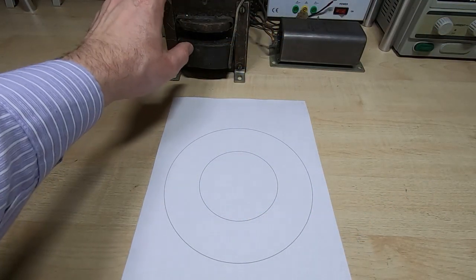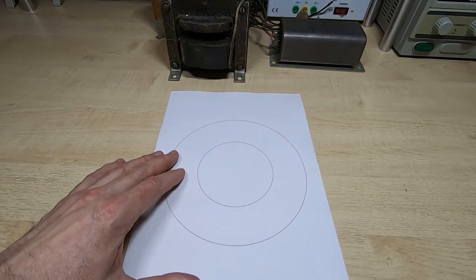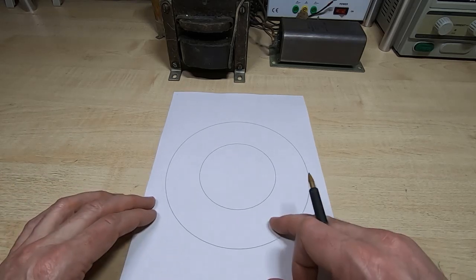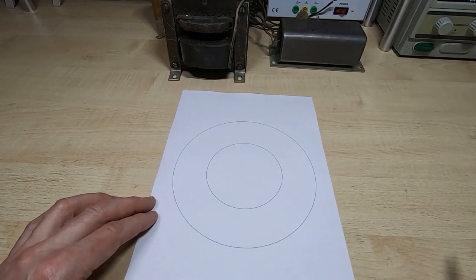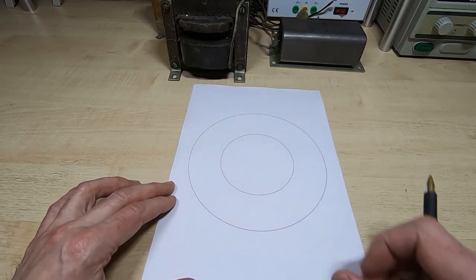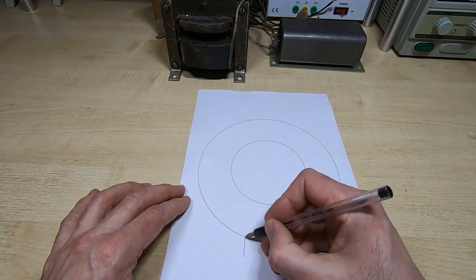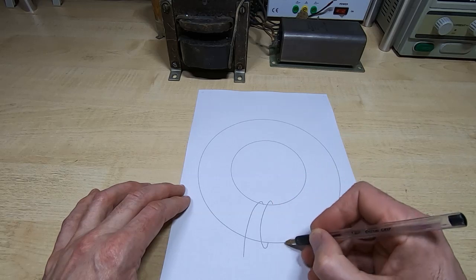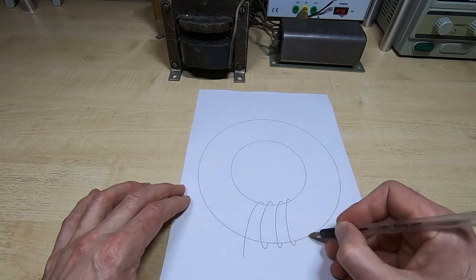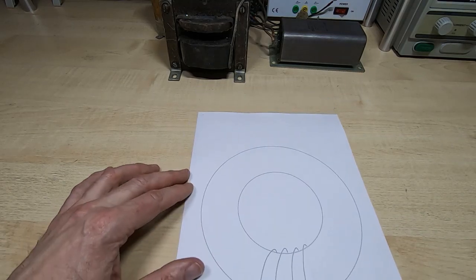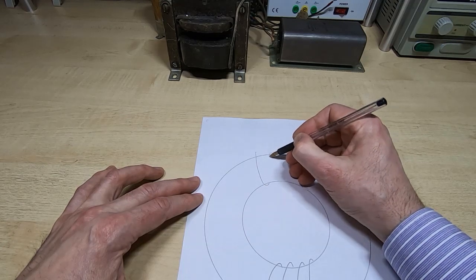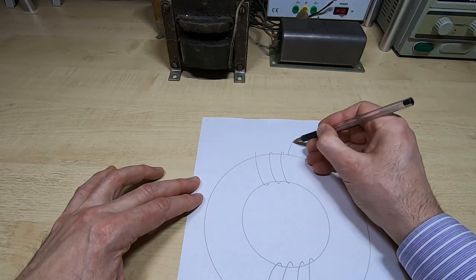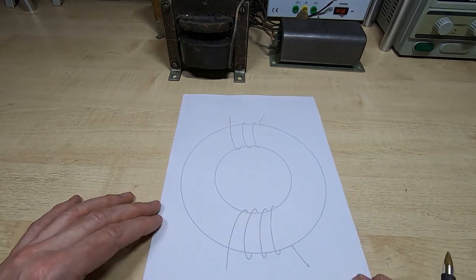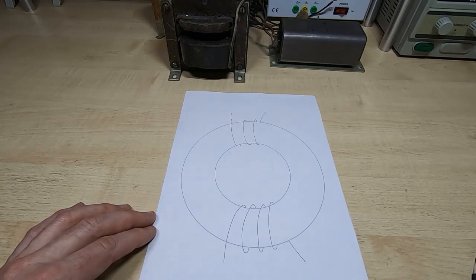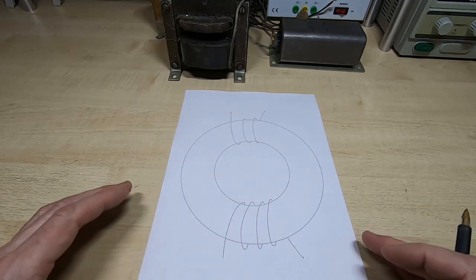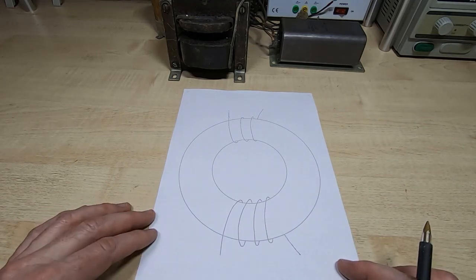To best explain how a ferroresonant transformer works, it will be easier if we first start by recapping on how a standard transformer works. So if you imagine this is the core of a standard toroidal transformer, then the transformer is made up from the core and at least two windings. So we have the primary winding, and then we have the secondary winding. Okay, so exactly how these are arranged on the core is not particularly important. They might be on top of each other, they might be at opposite ends of the core. It doesn't really matter. As long as they're wound around the common core, then the transformer will work.